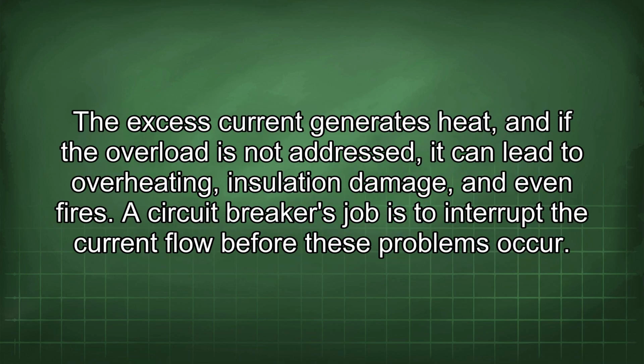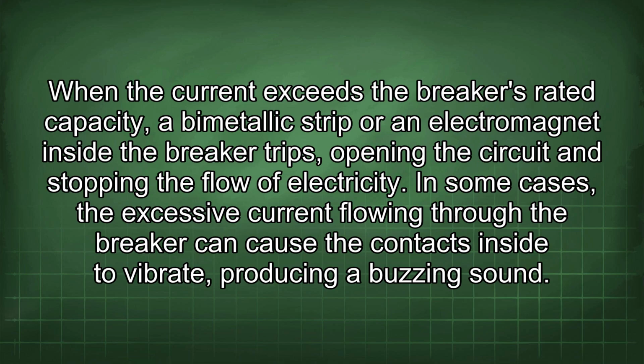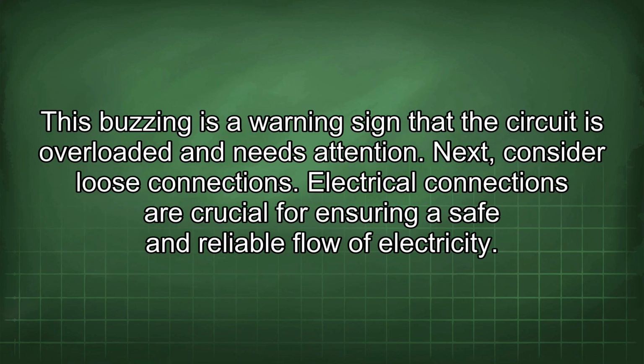The excess current generates heat, and if the overload is not addressed, it can lead to overheating, insulation damage, and even fires. A circuit breaker's job is to interrupt the current flow before these problems occur. When the current exceeds the breaker's rated capacity, a bimetallic strip or an electromagnet inside the breaker trips, opening the circuit and stopping the flow of electricity. In some cases, the excessive current flowing through the breaker can cause the contacts inside to vibrate, producing a buzzing sound. This buzzing is a warning sign that the circuit is overloaded and needs attention.